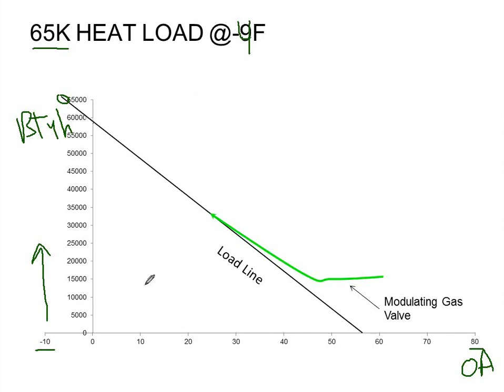Then what this furnace is going to do is the more mild it is outside, the more it's going to modulate its burner capacity downward. Right? If I only need 40,000 BTUs on a given day because it's 20 degrees outside, fine. I'm only going to run it at 40,000 BTUs. Now this furnace is not actually tracking the outdoor air temperature because that wouldn't make any sense, because everybody's house has different insulation values. So different outdoor air temperatures will require different BTUs for different houses. So what do you think we track instead of outside air to modulate this? We actually track space temperature, and more specifically, we track space temperature deviation from set point.